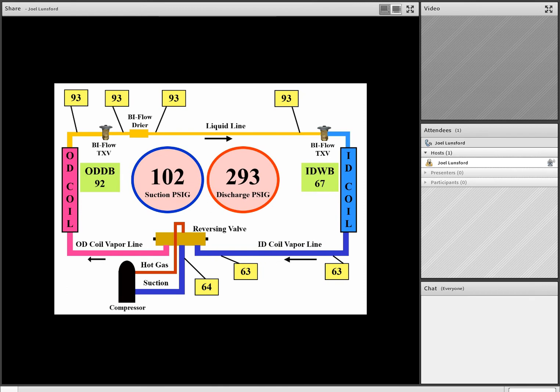Our suction pressure is low, our discharge pressure is low. Our superheat is high. Our subcooling is low. So both coils are starved. We have low subcooling. We have high superheat, low subcooling, and both pressures are low. This is a classic low charge.